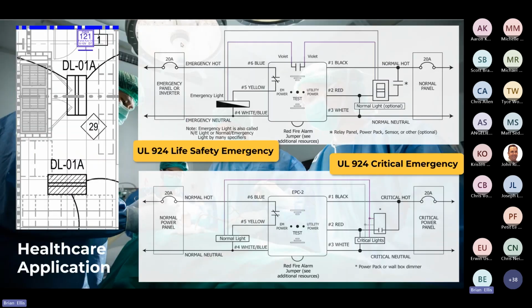Another kind of unique example that most people don't think about is healthcare. We look at growing verticals in our market today, healthcare, data centers, these kinds of things. Well, healthcare is everywhere. And something we're not really thinking very much about is we always think of these devices as our life safety path of egress devices. But in healthcare, you introduce an additional form of emergency called critical lighting. So critical is very different from path of egress. With path of egress, you want the lights to go on and meet your 1 foot candle average egress minimum, right? Some places are 1 foot candle, some are average or 1 foot candle, but you want to bypass the controls in the event of loss of utility.